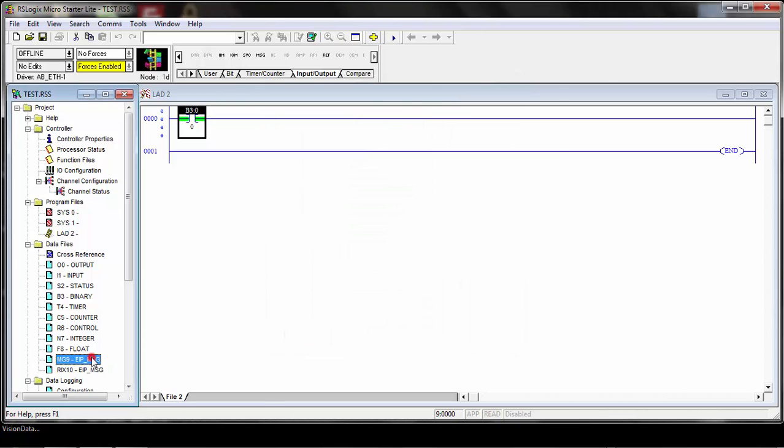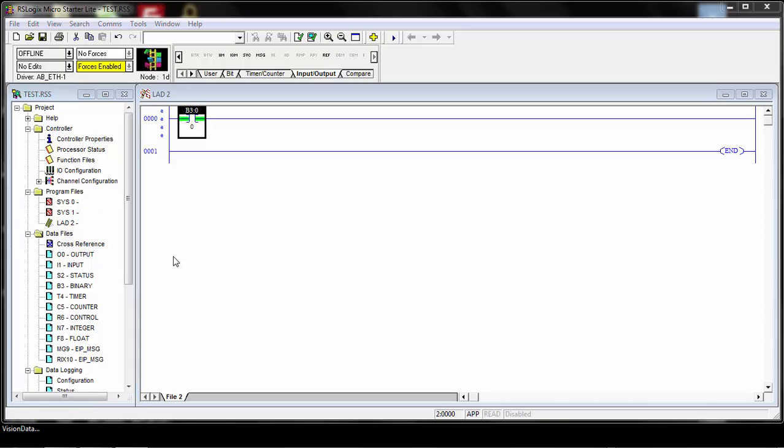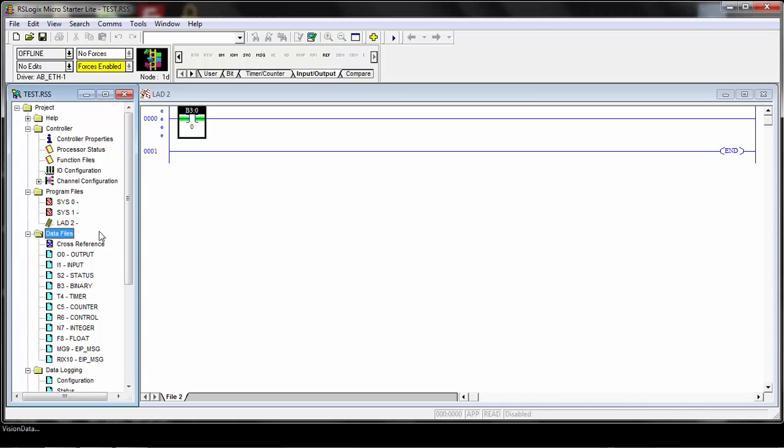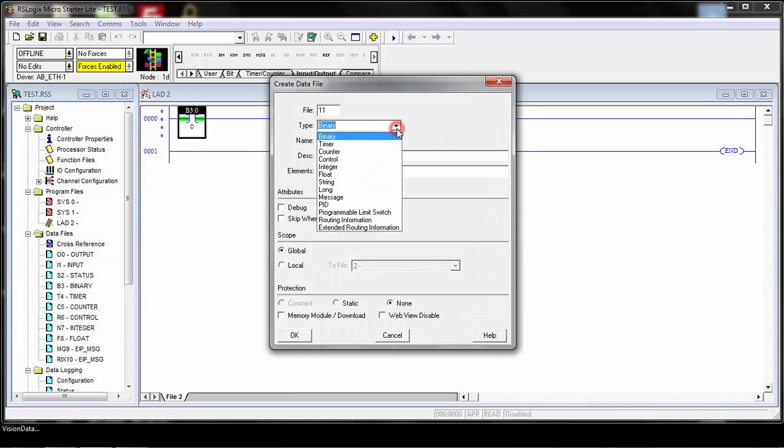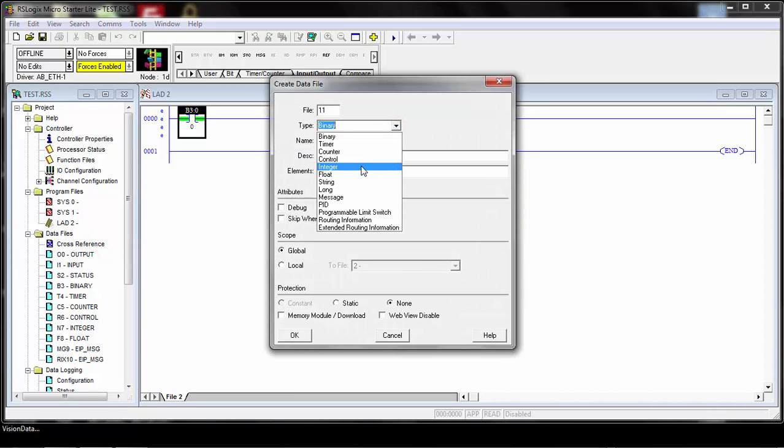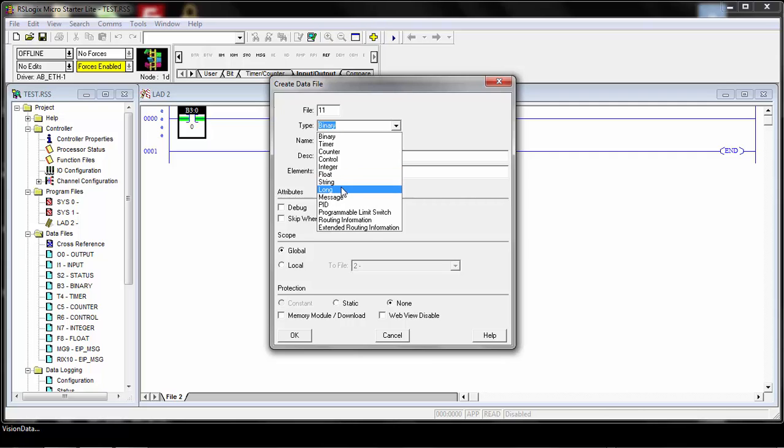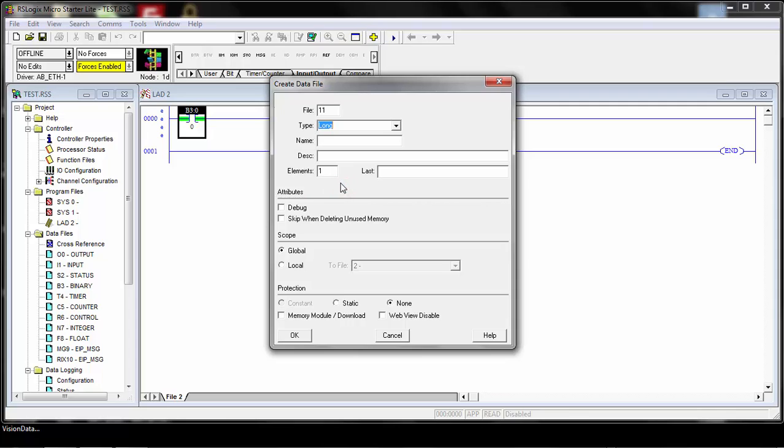You can see these have been added to the data files here. Next, we need to add some data files or data locations to be able to send and receive information when we create our messages. Right-click on the data files and click New. There's a couple different options for the types here. You could use Integer, which is 16-bit locations, or Float, which is single precision floating point locations. But the easiest thing to do with Ethernet IP communication is use the Long type. What this will do is create 32-bit locations to store, send and receive from, because a lot of stuff that you work with when you're working with Ethernet IP is 32 bits.